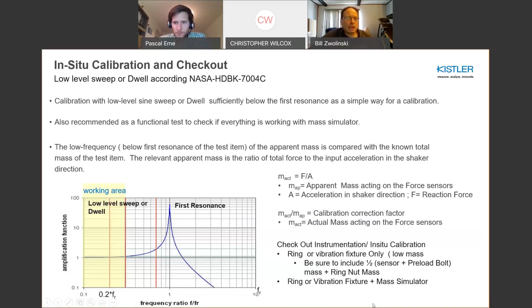Lastly, using static masses, for large 2.6 meter or 102 inch platforms, it's really not practical to use a static mass, but certainly conceptually you can use a static mass to calibrate. Simply put a mass on, put the charge amp in operate, take the mass off, and you'll see a change in the force reading. That should be directly proportional to the amount of mass that was removed. So pretty straightforward.